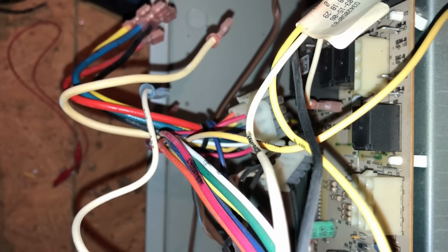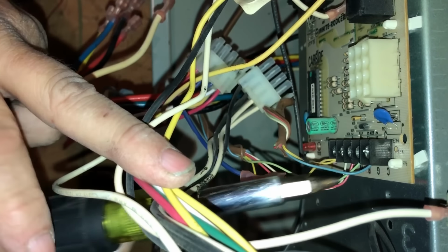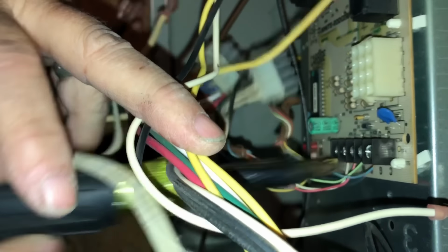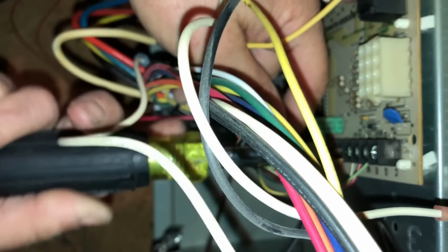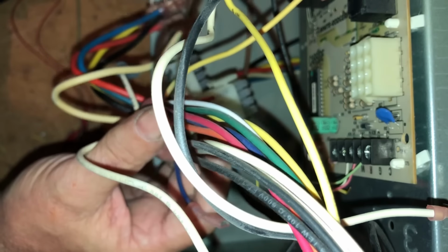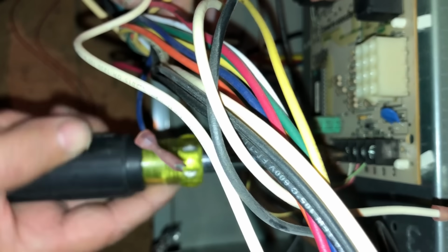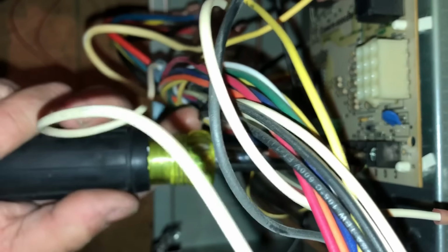One thing I learned a long time ago, you can save yourself some trouble by just noticing how the low voltage wires are connected, because as logical as some of us may like to be, someone else may have hooked some funny colors up. And on the 2-wire, it's pretty hard to mix that up because it's just 2, but they use blue and yellow, and I'm not going to say most, but I'm going to say a lot of people use red and white going outside.